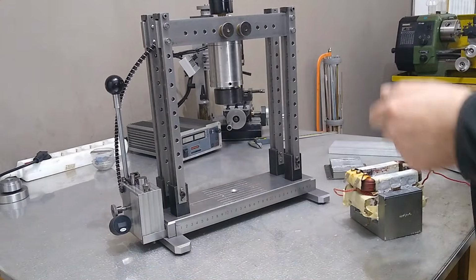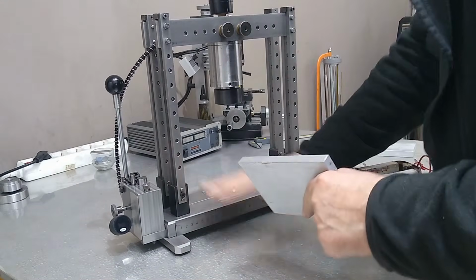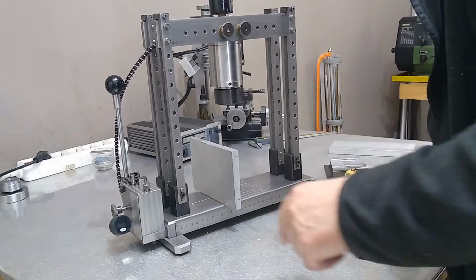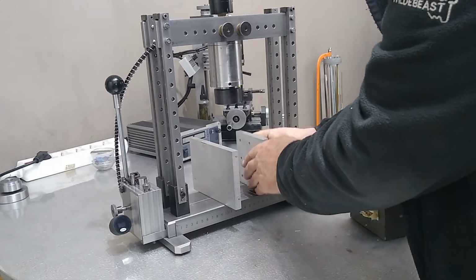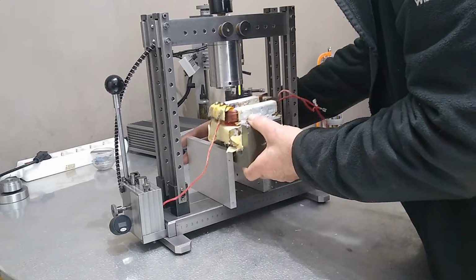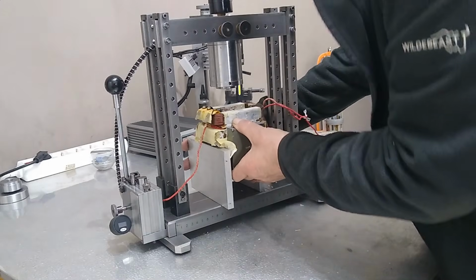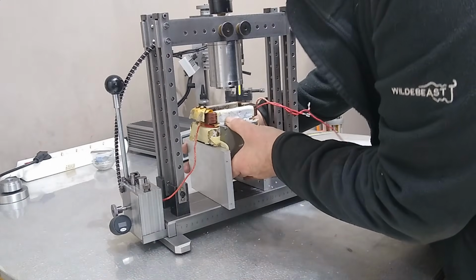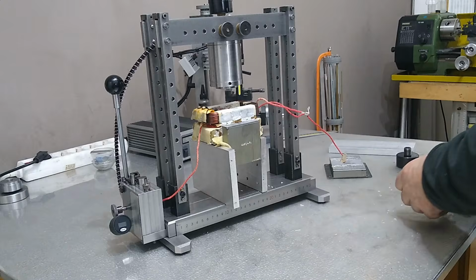My own estimate is that perhaps 500 watts will actually make it across. That changes the arithmetic: 500 watts divided by 3 volts gives about 166 amps. After accounting for additional losses, I arrive, by the highly scientific wet finger method, at roughly 150 amps at 3 volts AC.